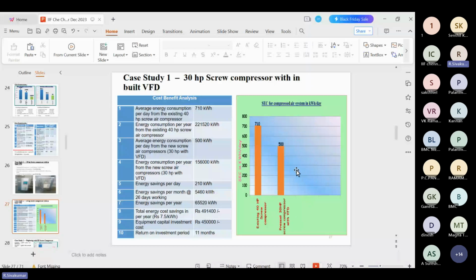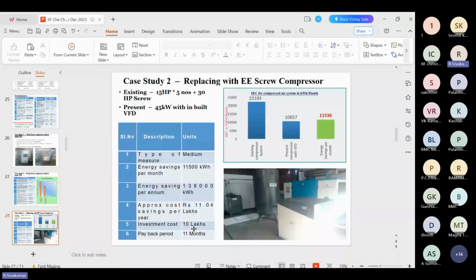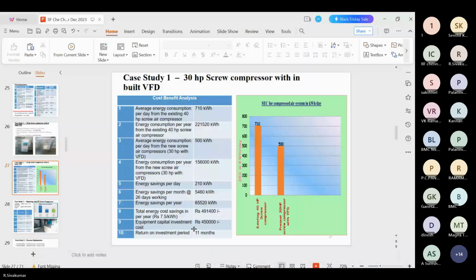So the summary of the implementation: the existing 40 HP was replaced with the 30 HP. Every day 210 units were saved, and in a year nearly 65,520 units were saved, and the cost saving is 4,91,400. The capital investment is 4.5 lakhs. The payback period is only 11 months for the implementation.